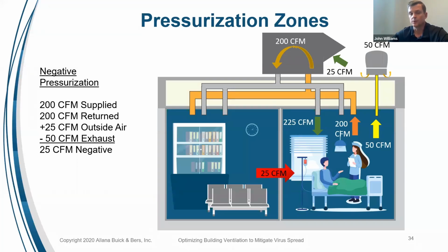I go to a lot of buildings where I'll just say the exhaust fans are not running because maybe we don't view them as critical, but they are critical because they may be controlling the pressure in the building. Same thing with our outside air dampers. Maybe they're viewed as not being critical, but they probably are critical not only for fresh air, but also to control our pressurization zones in the building.